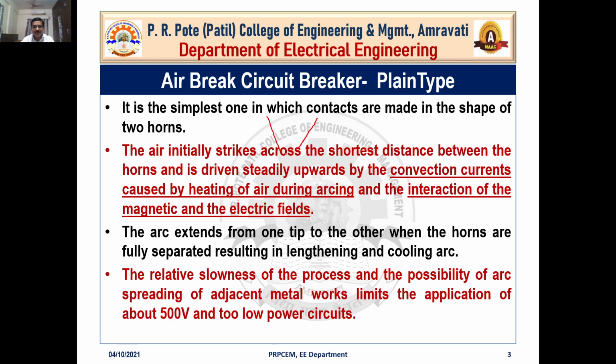This kind of arrangement we are preparing in order to lengthen the arc or to further cool the arc, and that way we are trying to increase the resistance of the arc, which will help to reduce the current and help to extinguish the arc. Here the arc initially strikes across the shortest distance between the horns. So this is the shortest distance of this particular arc.